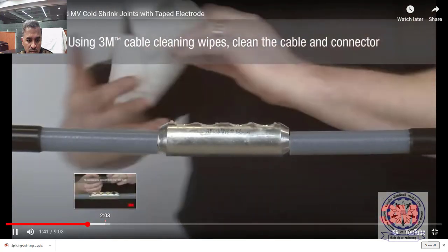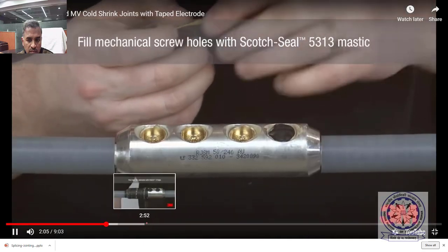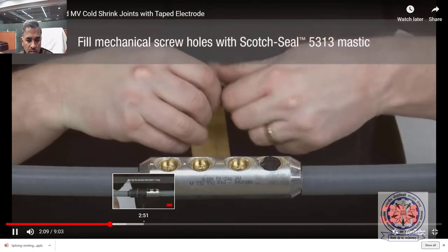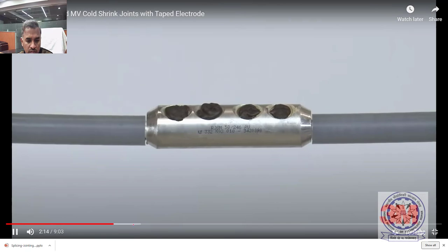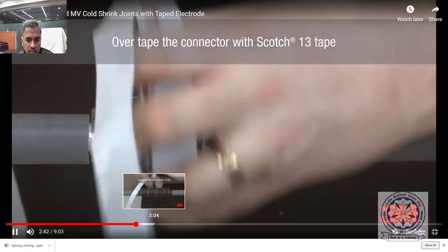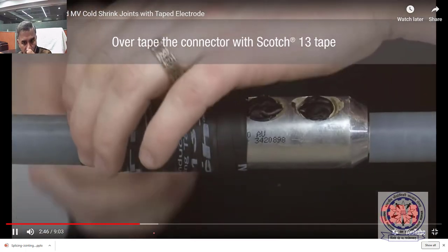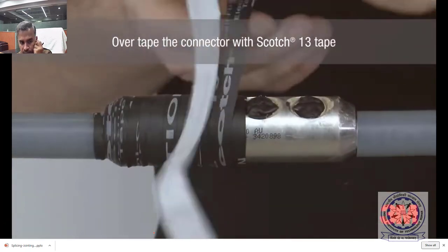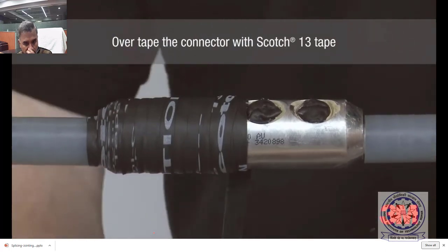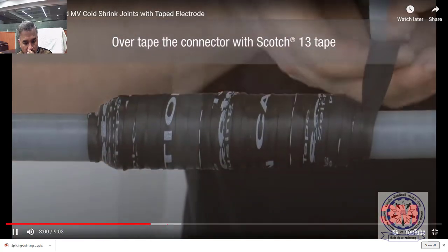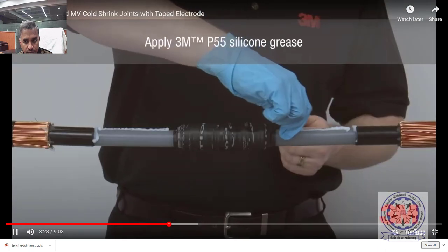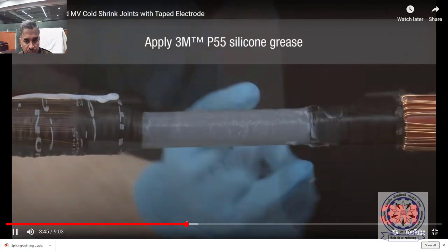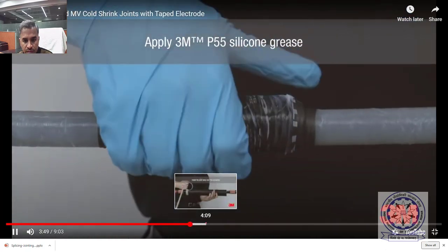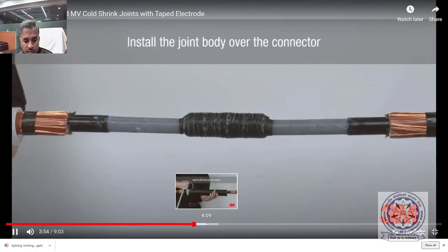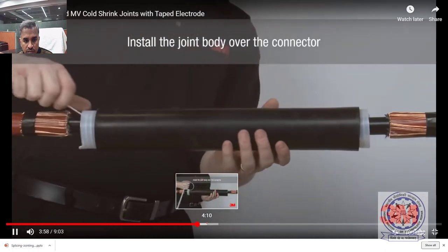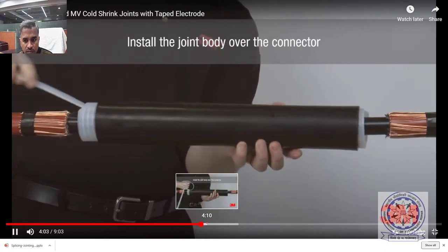Cable cleaning wipes are then used to remove dirt and grease from the cable and smooth out the connector profile. Remembering to leave the connector till last to avoid contamination. The joint body is then installed. These products are cold applied and therefore quicker, easier and safer to install than heat shrink alternatives. And they are also ideal where hot work permits are difficult to obtain.